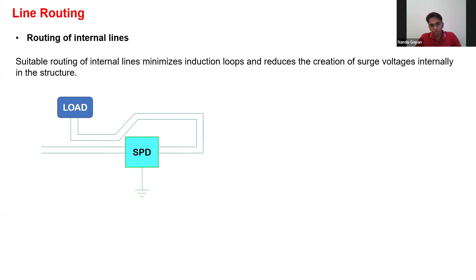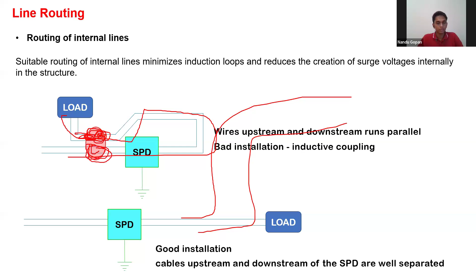Now, line routing - how we are supposed to do it. Line routing is very important. You are not supposed to route lines in a way that induces voltage in the line. So if you have an SPD and a load, you're supposed to route it properly, or do some turnings, bringing it around. But you are not supposed to route it directly facing the strike path in certain fashions - this is not advisable, because if there is a lightning strike, due to the induced current, induced voltages can appear in that place. It is quite dangerous.